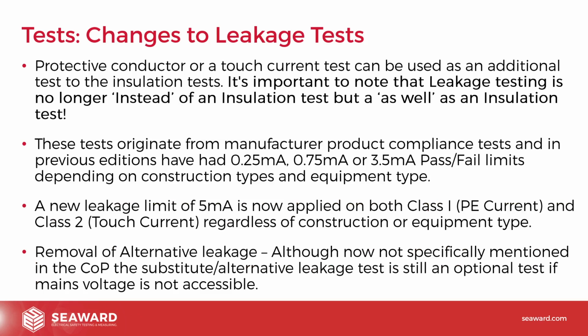So, changes to the leakage tests. Protective conductor or touch current tests can be used as an additional test to the insulation test. It's important to note that leakage testing is no longer instead of an insulation test, but as well as an insulation test. I'll talk in a moment about a new flow chart that's been added in. This was an important change because in the past you could do an insulation resistance test or you could do a leakage test. It was perfectly acceptable to do one or the other. It wasn't one and the other.